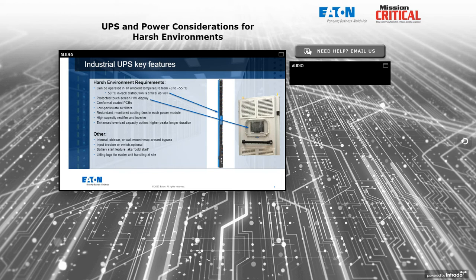Now, as you probably know, lithium batteries, for example, do operate successfully over a typically wider temperature range than do traditional lead acid or valve regulated lead acid UPS batteries. However, it is still wise to keep that temperature within a range of about 65 to 85 degrees Fahrenheit, because the longer service life and warranty that comes with a typical lithium battery installation is based on a reasonable temperature range. So yes, if I have to operate at a much higher temperature range, maybe 35 C or 40 degrees C, then a lithium battery will give you better performance than a traditional UPS battery. However, if you want that full service life from the lithium battery that you're typically paying extra for, then you need to make arrangements to keep that temperature in a reasonable range.